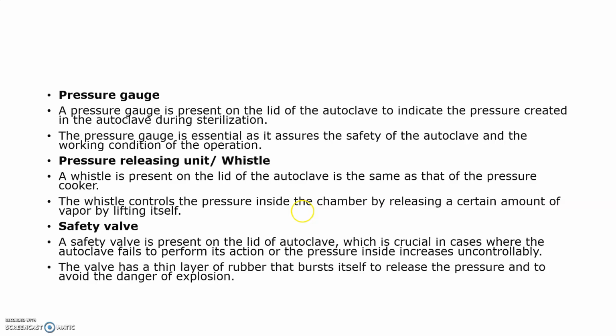The pressure gauge is present on the lid of an autoclave. The pressure releasing unit or whistle is the same as what we see in a pressure cooker, and it controls the pressure inside the chamber by releasing a certain amount of vapor by lifting itself. The safety valve is also present on the lid of the autoclave.